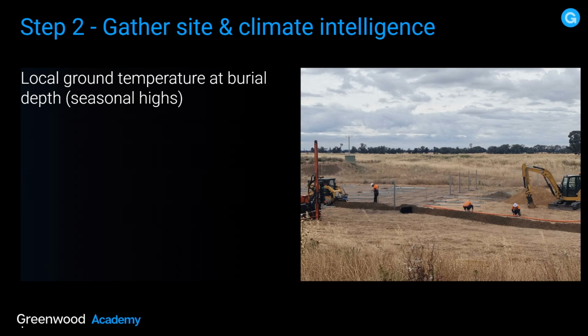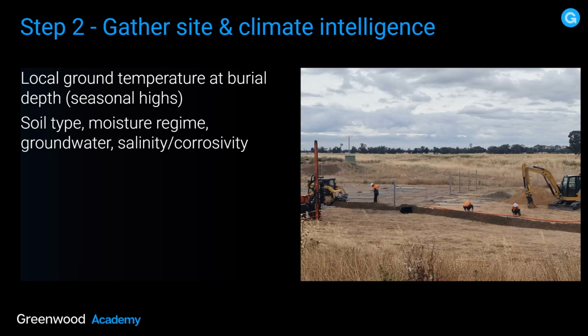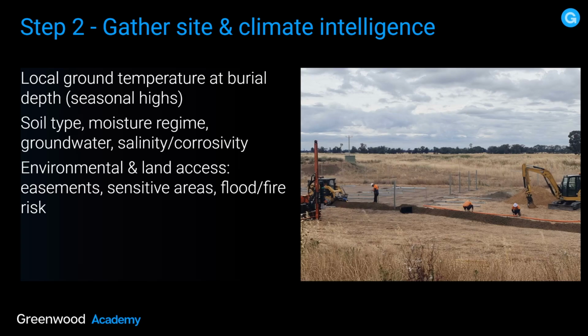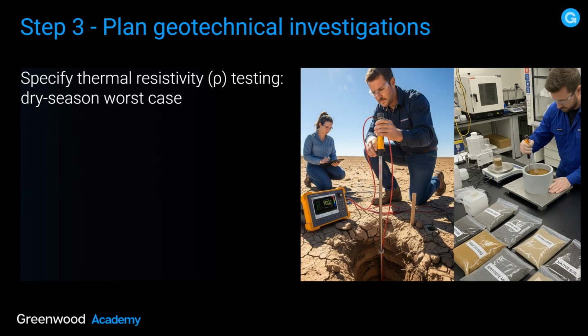Now, step 2, gather site and climate intelligence. So we're talking about local ground temperatures at burial depth and also the seasonal highs and lows. More seasonal highs, that's where you should be doing your calculations. The soil type, the moisture regime, the groundwater, the salinity and the corrosivity. Environmental and land access, easements, sensitive areas, flood and fire risk. Step 3, plan the geotechnical investigations.